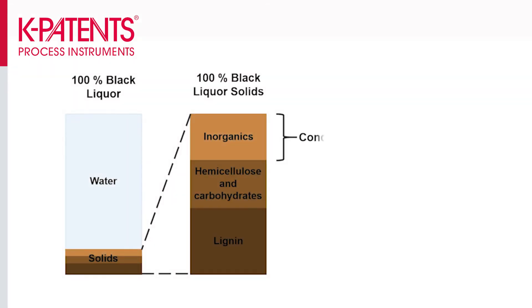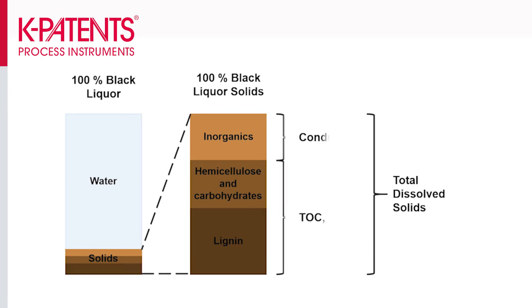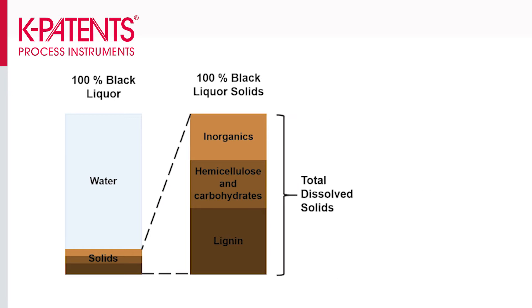While conductivity measures the inorganic changes, the COD laboratory test gives indication on the organic fraction of the total solids. COD has its place in the laboratory but it cannot be used for process control due to the considerable delay and labor involved. Total dissolved solids has proven to be the most suitable and most reliable parameter for measuring wash loss and washing efficiency, because it considers all washable solids — the organics and the inorganics. This is the only true measurement of wash loss.